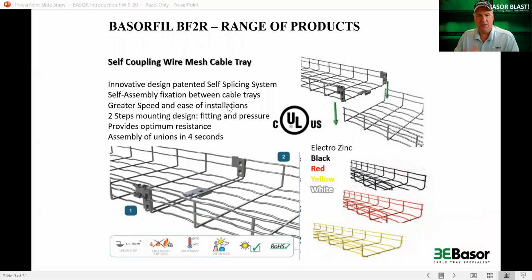Waving the longitudinal wires functionally stiffens the wire, so we can reduce the amount of steel necessary to carry the volume load of cables in the tray without large deflection. If the wires aren't bent or stiffened, you'll have a problem. By stiffening them through our unique waved wire, we're able to take out waste—wasted steel, wasted energy, wasted weight—which impacts cost for shipping, installation, and the original manufacturer.